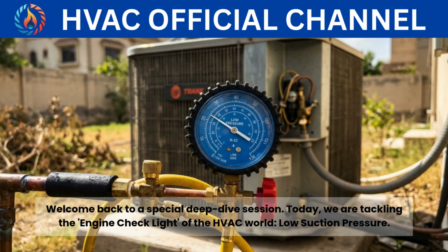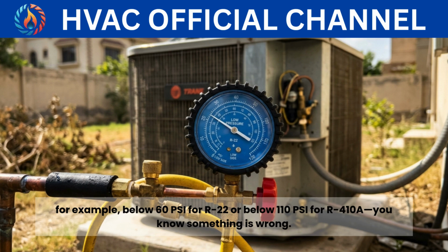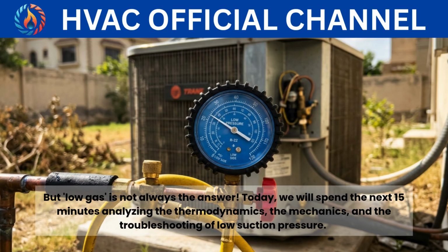Today, we are tackling the engine check light of the HVAC world, low suction pressure. As a technician, when you hook up your manifold gauge to the suction pipe and see the needle sitting below the normal range, for example, below 60 psi for R22 or below 110 psi for R410A, you know something is wrong. But low gas is not always the answer. Today, we will spend the next 15 minutes analyzing the thermodynamics, the mechanics, and the troubleshooting of low suction pressure.